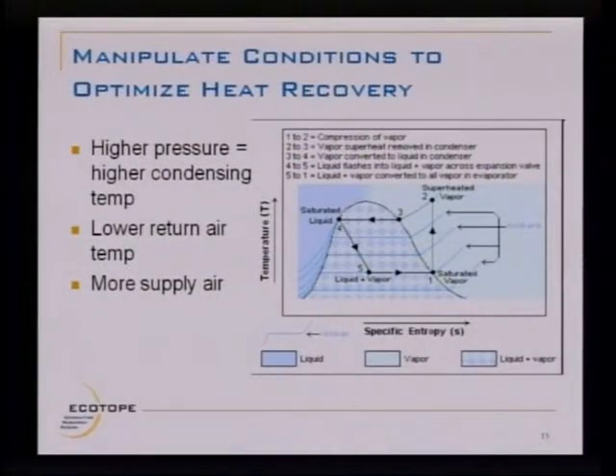The other thermodynamic concept to remember here is that heat will only naturally flow from a warmer body or a warmer area to a colder area. So you have to manipulate the conditions in your coil, in your air handler, to make them advantageous for heat recovery. If you put 70-degree refrigerant into a coil in your air handler, you're not going to get any heat out of it. I don't care how much heat is theoretically available in that refrigerant. It can't go from the refrigerant into the air unless it's significantly hotter than the air that's flowing over the coil. And it's not going to condense in that coil unless you can bring the temperature of that refrigerant down to the point where it starts to condense.